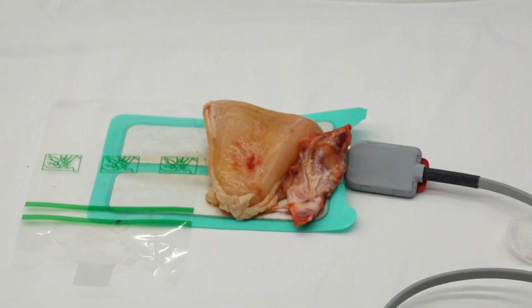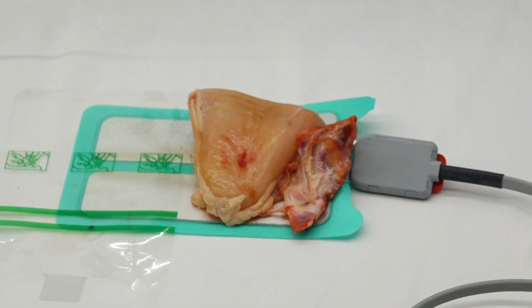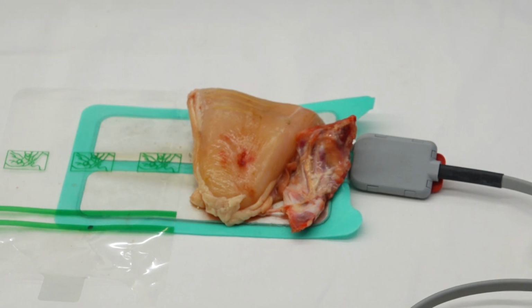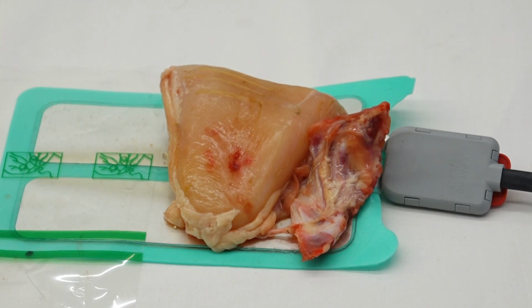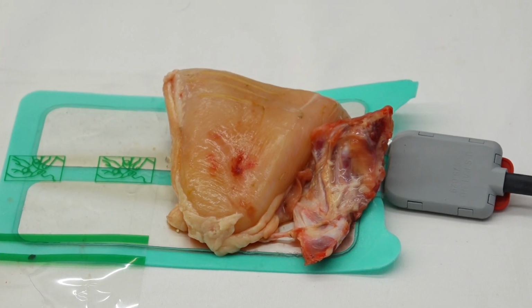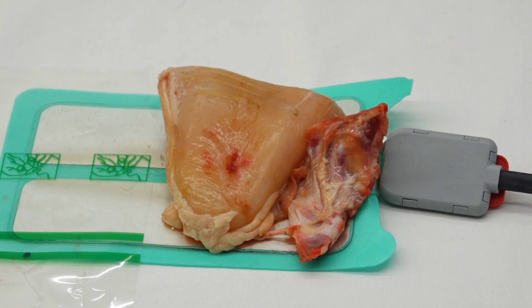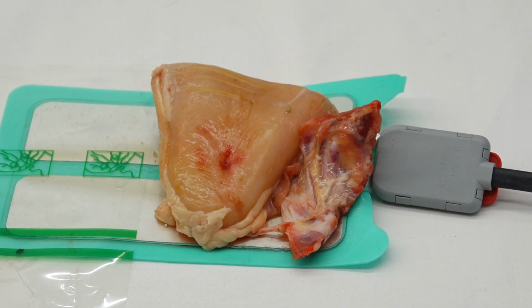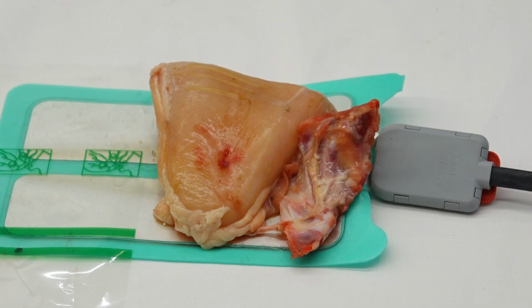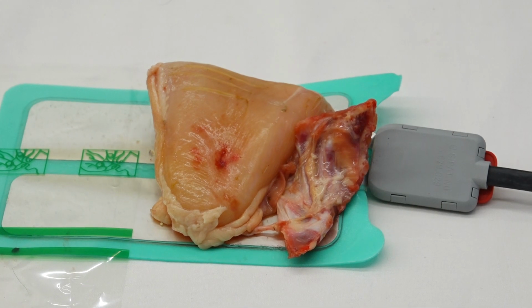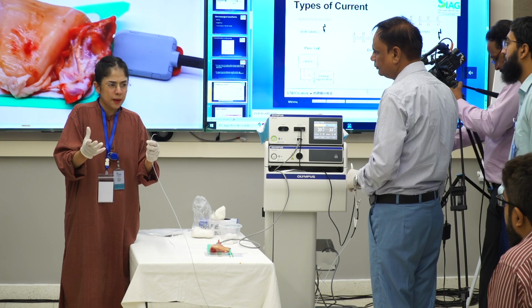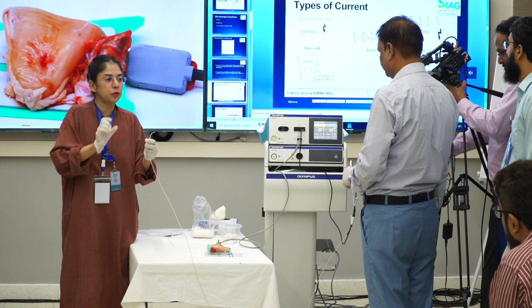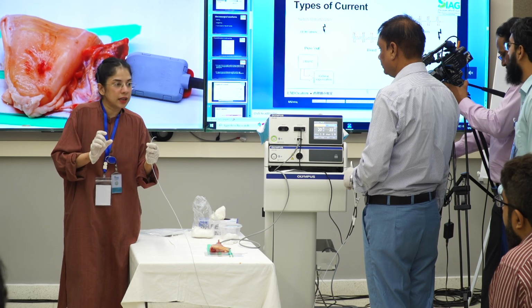And if you press the pedal on a pure cut, you will notice there's only a unified tone that comes. There's no interval tone. Those tones are basically there. That's why, if you're doing endocut and you press the pedal and the sphincterotomy is on, if you keep taking your foot off the pedal during endocut, you're actually usually just cutting. You're not introducing the coag. And that is why intermittent pedal pressing in the middle of an endocut usually results in bleed, and usually minor bleed, because you're not introducing the right amount of coag. Okay? You're giving it intervals.